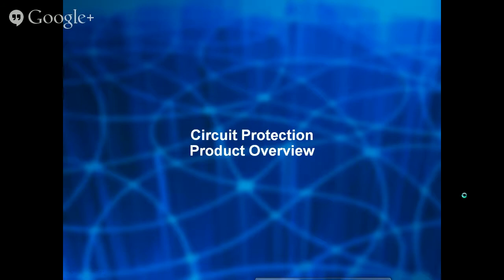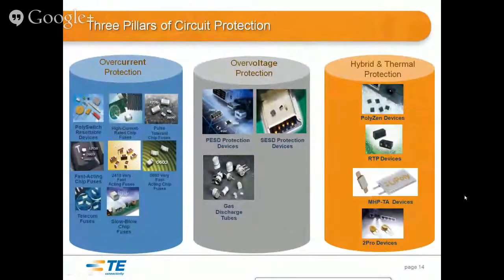In our world of protection devices, we classify products into three categories: over-current protection, over-voltage protection, and hybrid/thermal protection. Over-current protection refers to any device whose resistance goes up during a fault condition. In the case of fuses, they go to a complete open circuit — everybody is familiar with fuses, they work well, but when they open they have to be replaced.